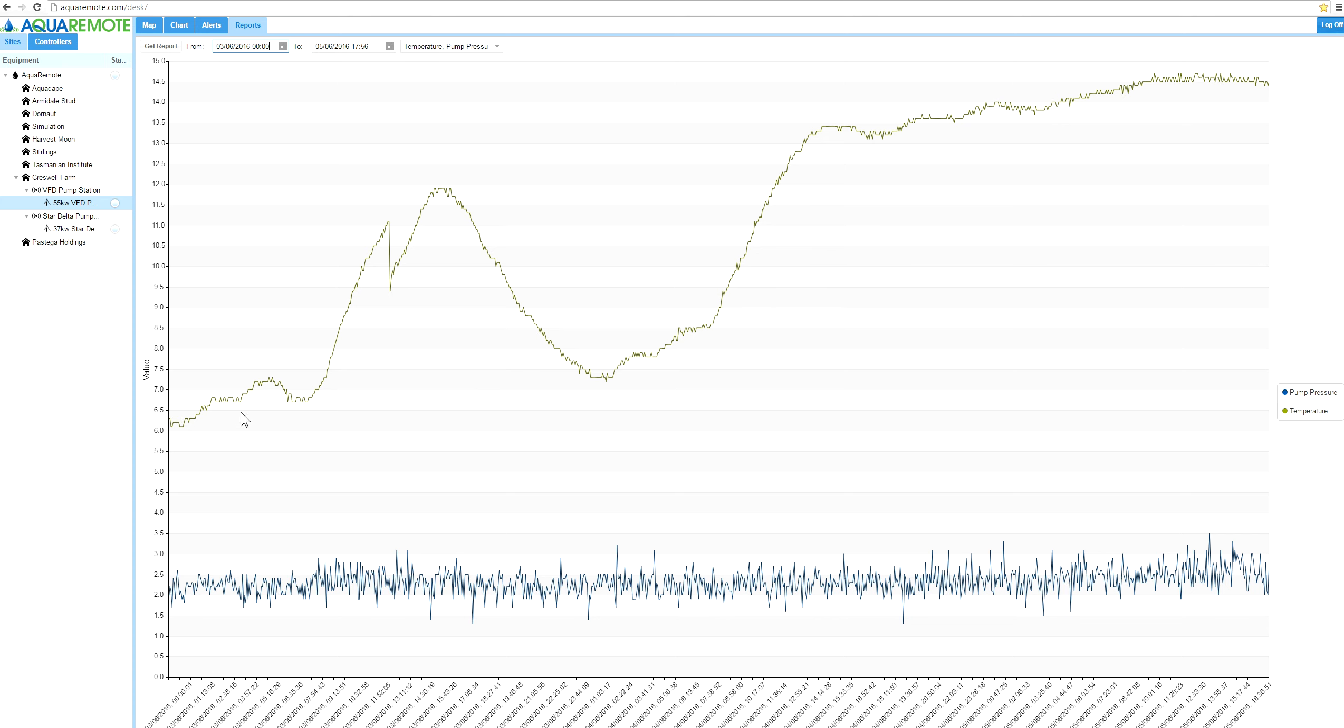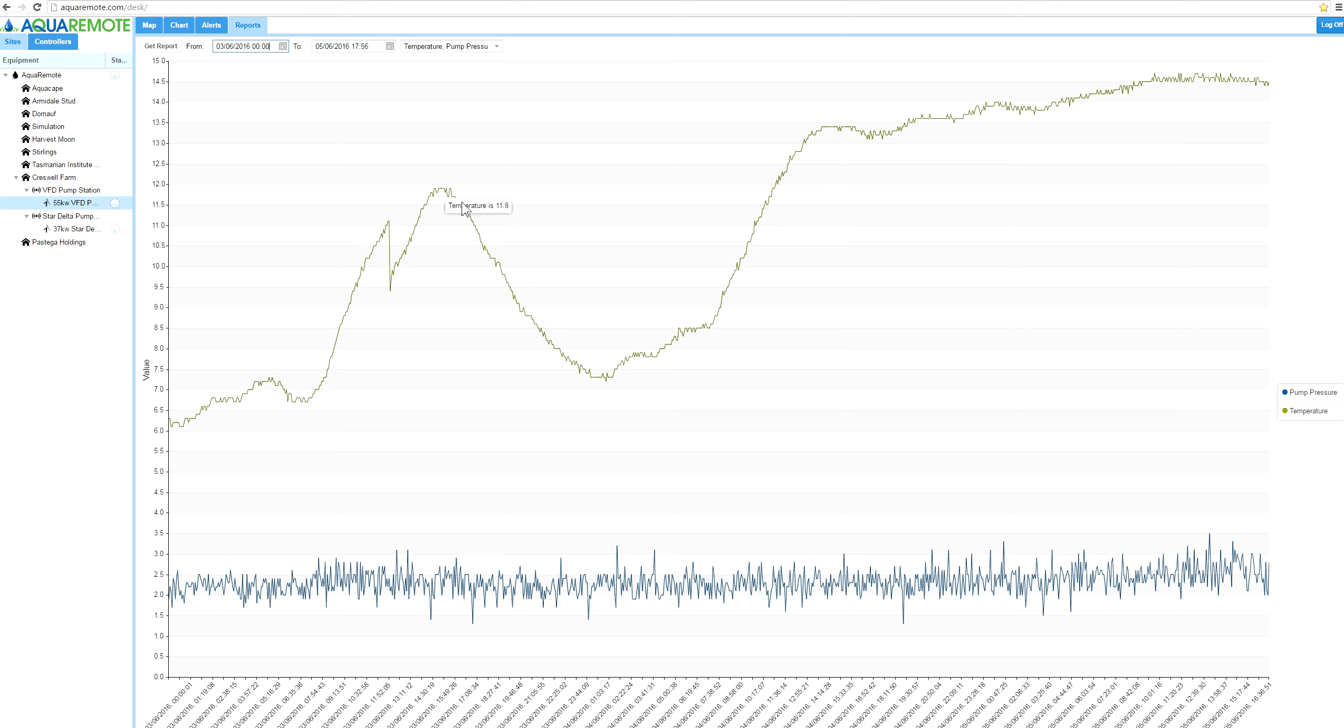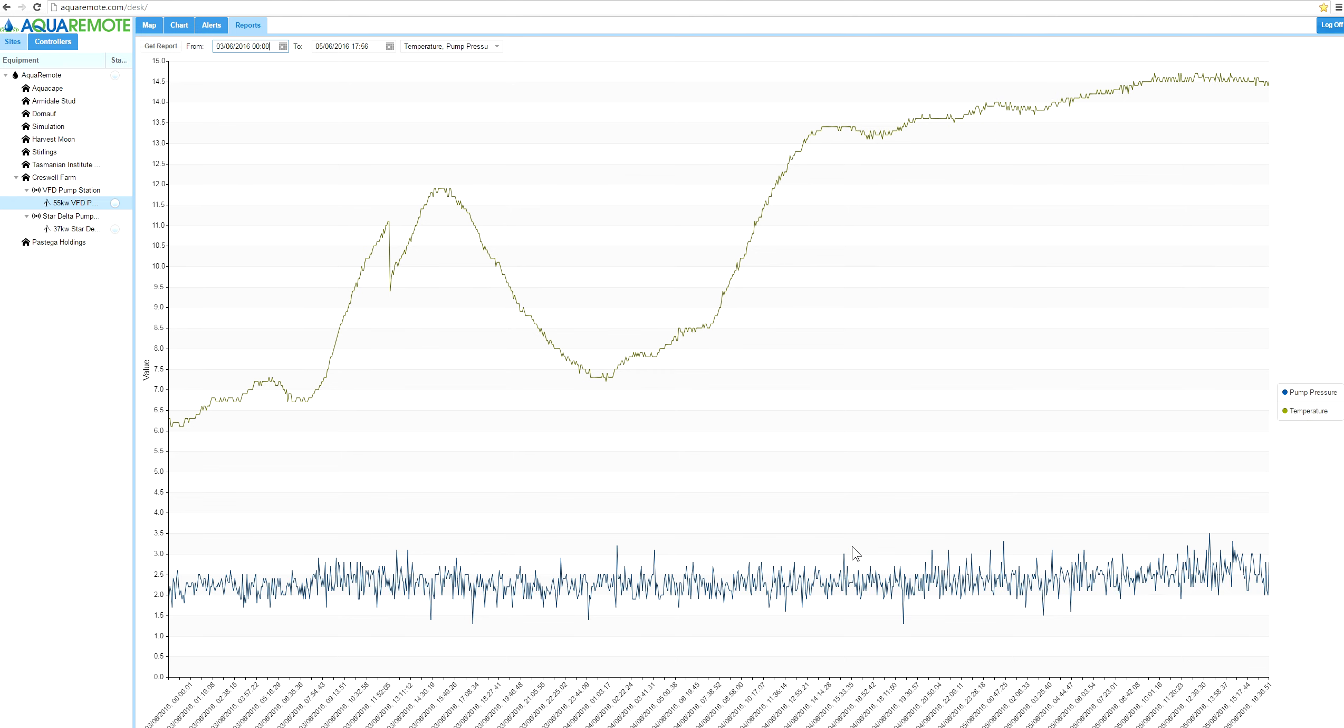Okay, so here we go. You can see here that the pump set's around six degrees, ten degrees, eleven degrees, back overnight again, then up through to this period of time now. It also shows pump pressure. This isn't very high because it's just in standby, but you would see a rise in pressure when the pump was started. You can use this data for all sorts of things.